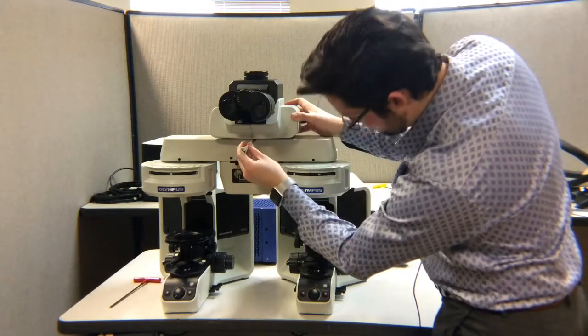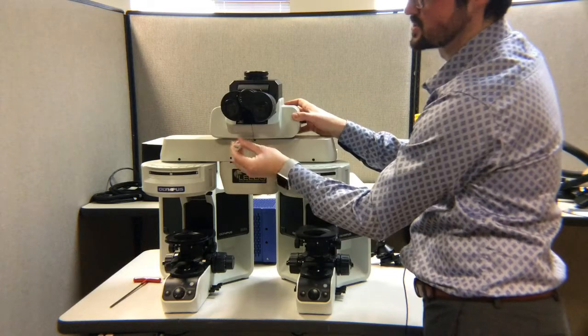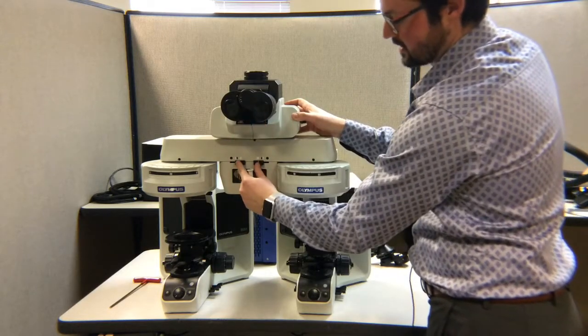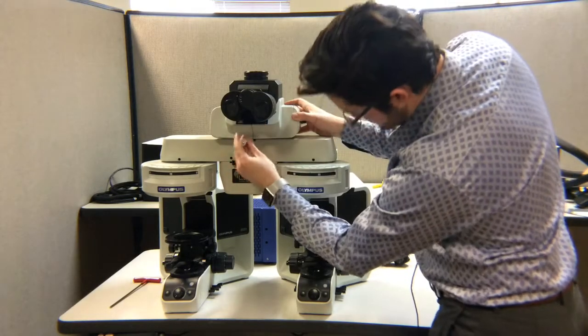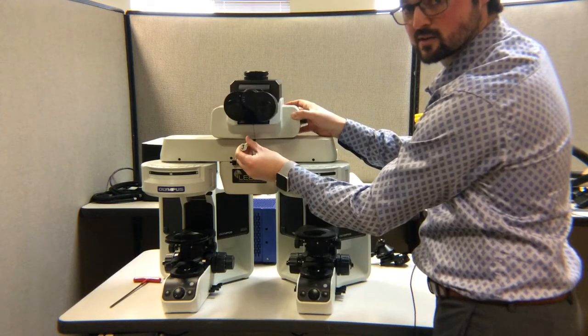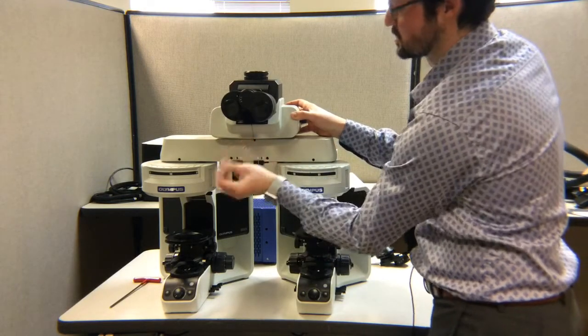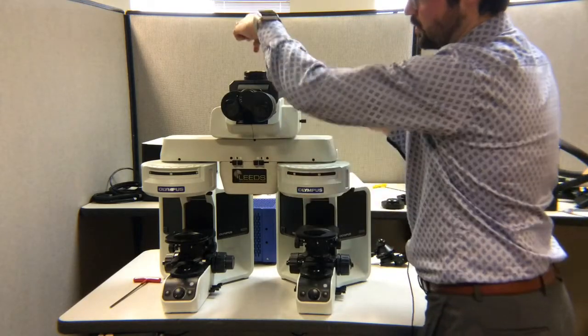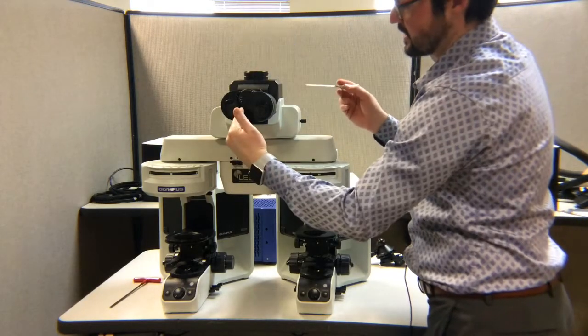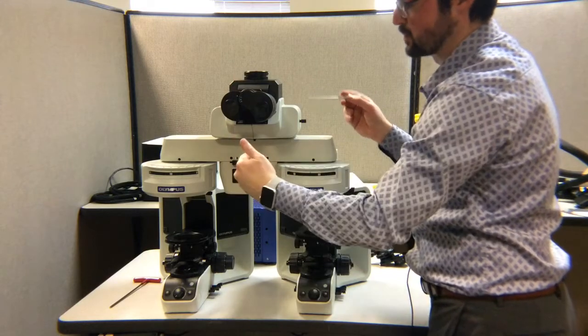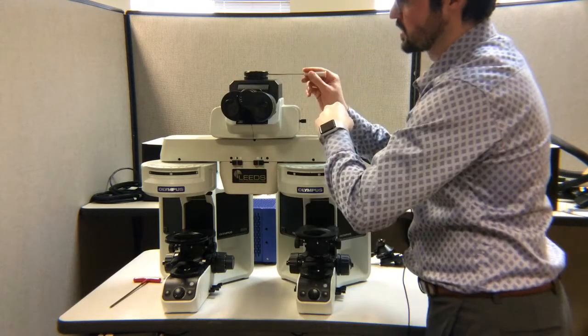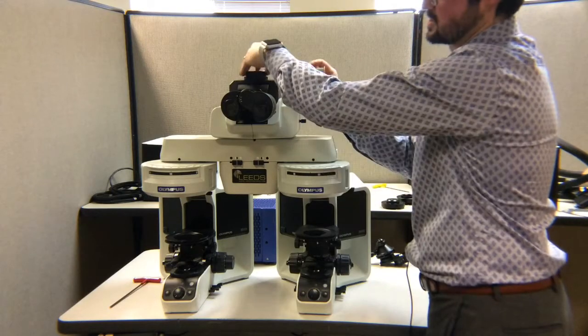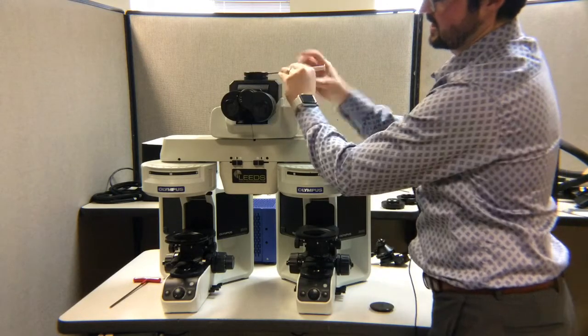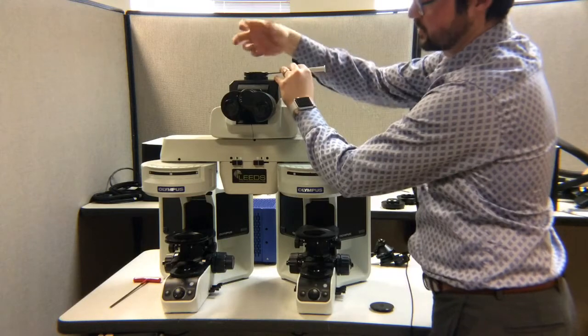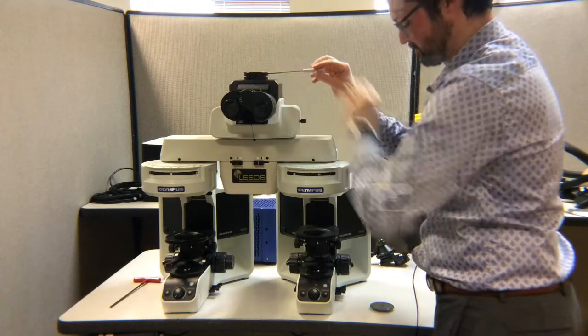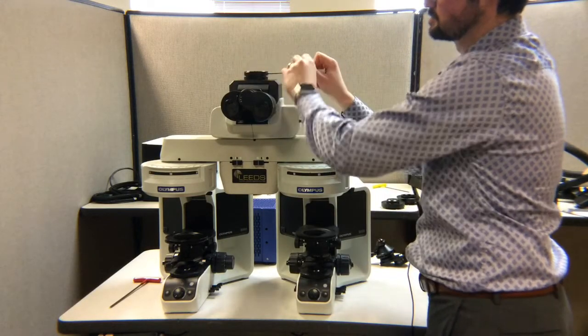So on one of the final steps on setup, what you'll want to do is just put two eyepieces in, put the dividing line in the middle of the bridge, and then adjust the angle of the trinocular to get that dividing line straight up and down. Similarly, when you mount the camera on here, if the dividing line is vertical, straight up and down, but then the camera dividing line is crooked, you can adjust the camera's dividing line by adjusting this, which is called the photo port, and this is where the camera will attach. And if you adjust that angle, or that twist, you can adjust the dividing line for the camera. But for now, we're going to go ahead and close that dust cap.